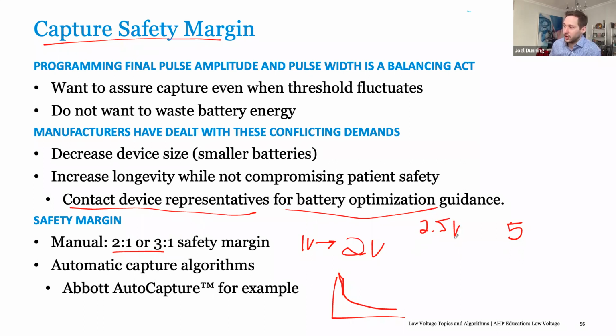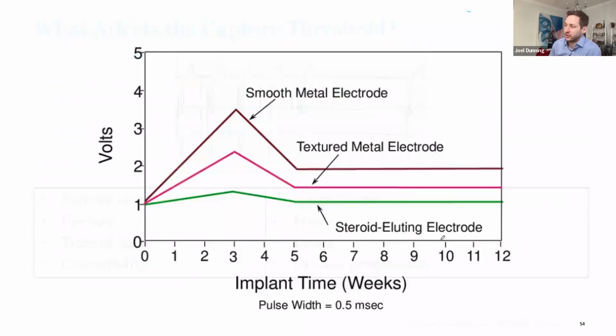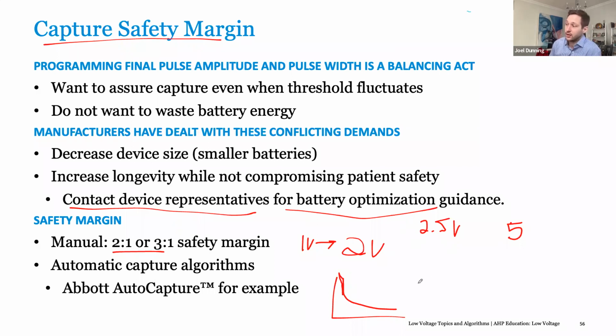If you can keep the voltage underneath 2.5 volts, you'll find that the battery lasts considerably longer, because the circuit board doesn't have to basically double the amount of energy being drained here. So, for example, if we assess the threshold at, say, 3 volts at 0.4 milliseconds, but the threshold is going to be, for example, at 1 millisecond, it's only going to be 1 volt, right? So in this case, it's actually advantageous to program the patient at 2 volts at 1 millisecond.